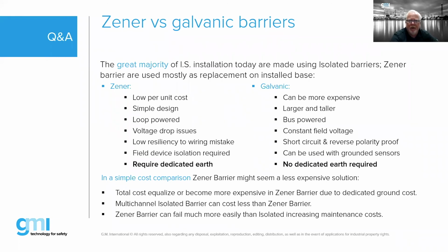Okay. Typically, historically, Zener barriers were less expensive than galvanically isolated products. Simple design, loop powered. The one big issue with Zener is, as we mentioned, the requirement of the dedicated earth. The galvanic ones are typically more expensive, and in many cases, because they do contain a transformer, they have typically been larger and taller. So density, if you will, when you have a panel with a lot of barriers, has usually been a big problem with galvanically isolated products. Now, GMI's new range is actually a much thinner product, so we've taken the disadvantage of a galvanic and made it much more in line with a Zener type product. You do have to power a galvanically isolated product, but again, we don't have that dedicated earth.